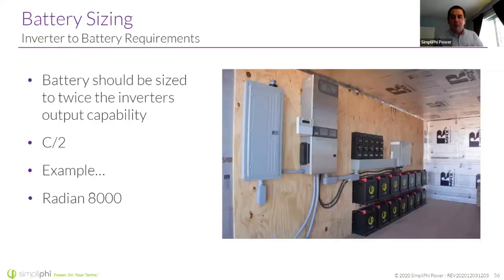So, a quick sizing example. This is an Outback Radian. It's an 8,000 watt inverter. We have a C/2 rating. So if I've got 3.8 kilowatt hour batteries, C/2 means they can do 1.9 kilowatts. If I do the math real quick, I'm going to discover that this Outback Radian needs at least 5 batteries to provide the power that that inverter is capable of. If you undersized it for less than 5 batteries, that could be a problem where the inverter pulls more than the batteries are capable of. The system is oversized. They've got about 14 batteries here, so they'll be able to provide whatever that inverter needs.